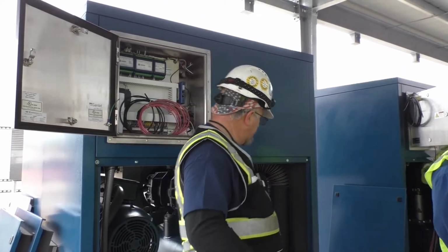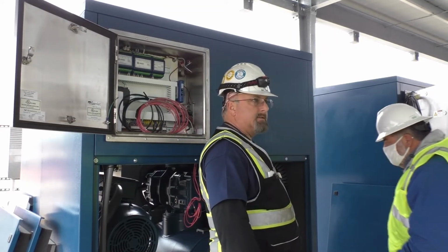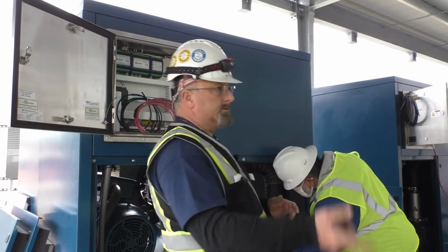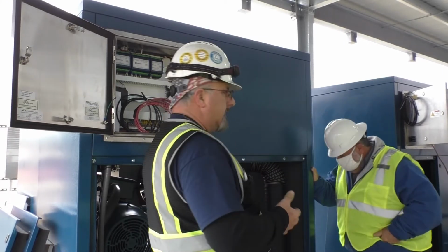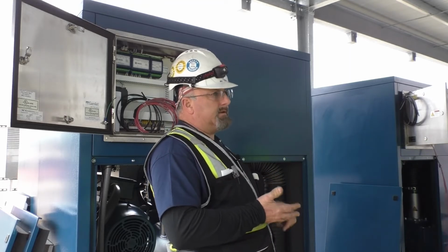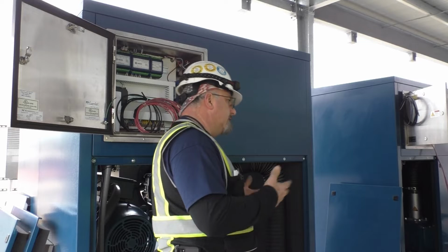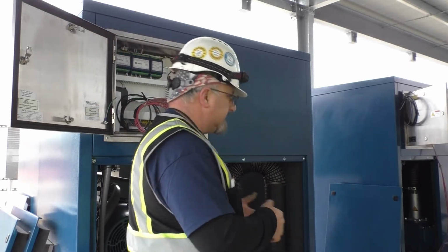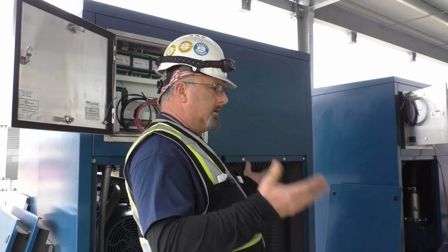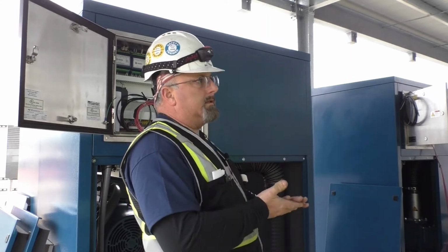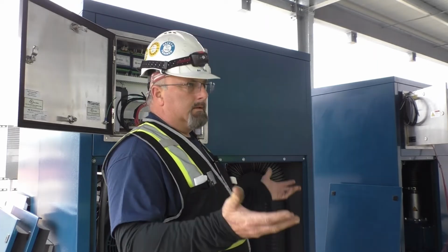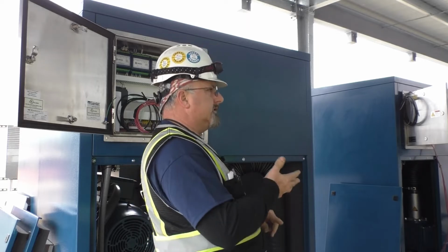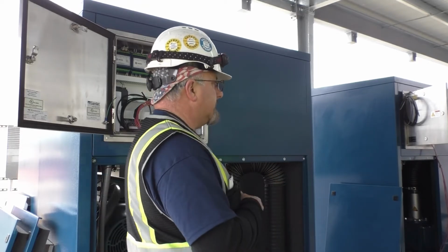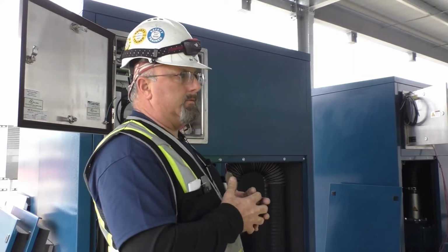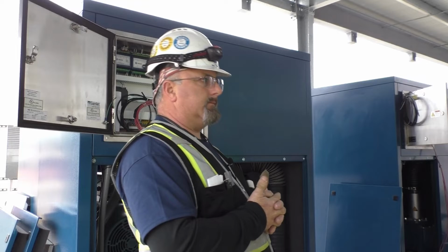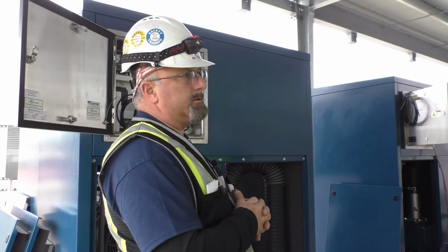That's for 2 reasons. Number 1, if you had any mice or anything get up in here and make a nest, or they get something on top of here, it blows all that out so it doesn't create any blockage. It also lets you know that the pressure relief valve is functioning, and it does reseal if it does lift. Because over time, due to just the heat cycles on them, the springs can, 15, 20 years down the road, lift at a PSI less than what the original design was. So that's why you check those, make sure they lift, make sure they reseal. Now, as far as an actual replacement interval, no, there isn't one. This inspection, if it fails or starts lifting early, then it needs replacement.